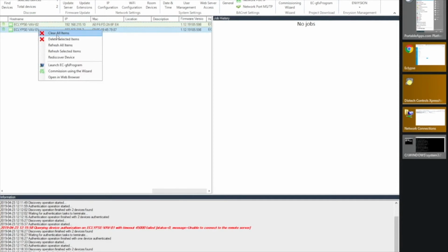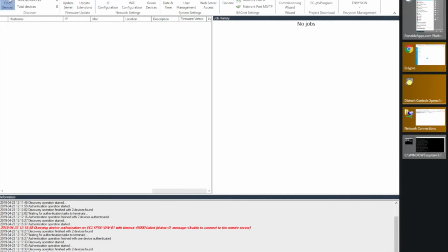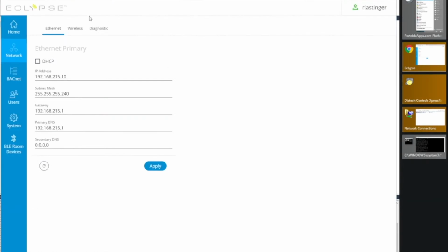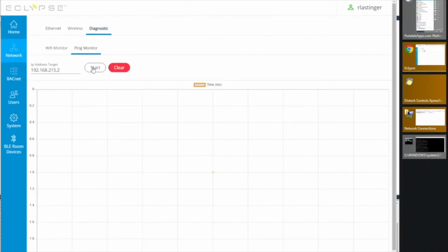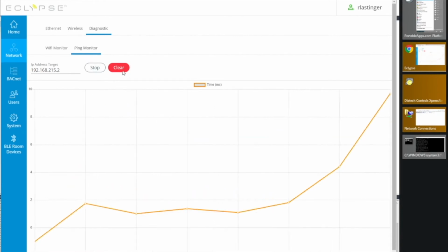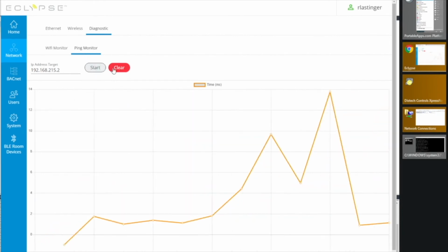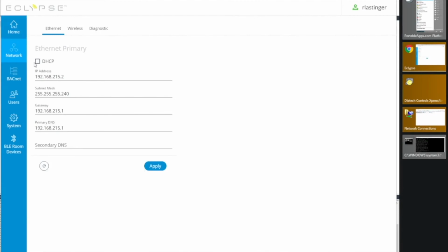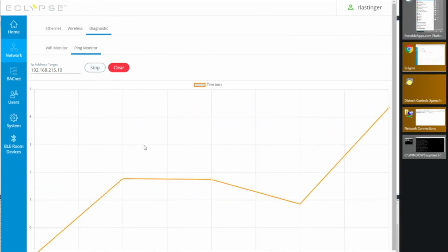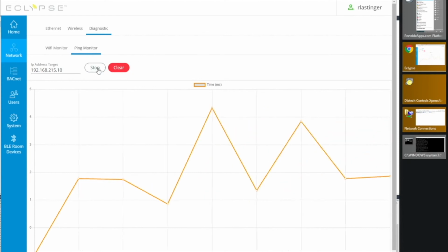So really what we're trying to showcase here is that when you're doing a job, you really should be using a subnet that's reasonably sized for the number of controllers you have. If you have 300 controllers, and you want them on a single subnet, then you should use the calculator and put 300 hosts in there and figure out what an appropriate subnet would be for 300 controllers. Also, if you have 6 controllers, you might leave yourself a little breathing room and say, okay, I'll have a subnet with 30 or a subnet with 14, but it doesn't make sense to have a subnet of 255.255.0.0 with thousands of potential addresses for 7 controllers, right?